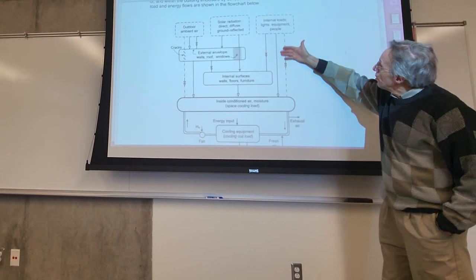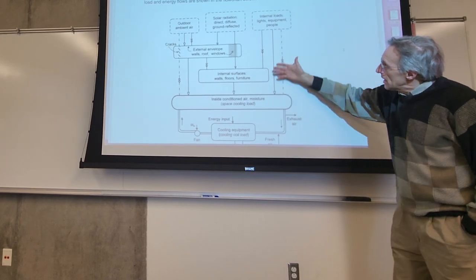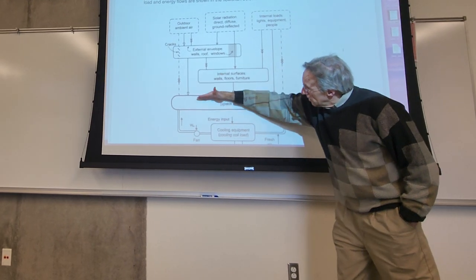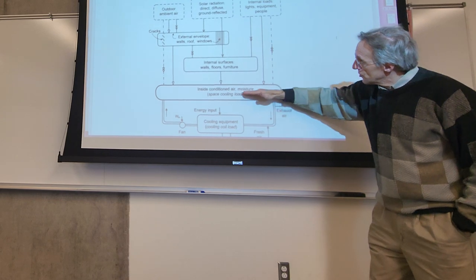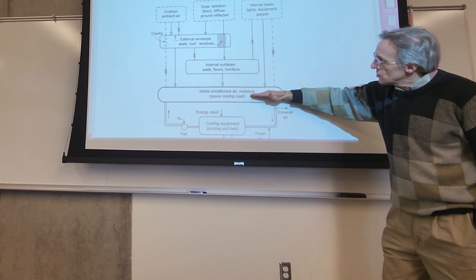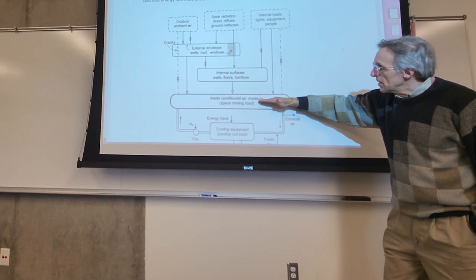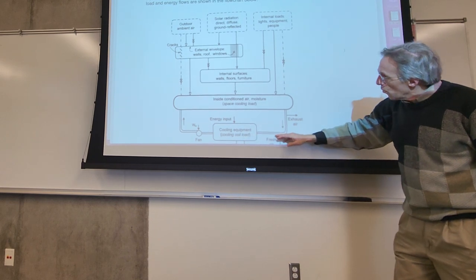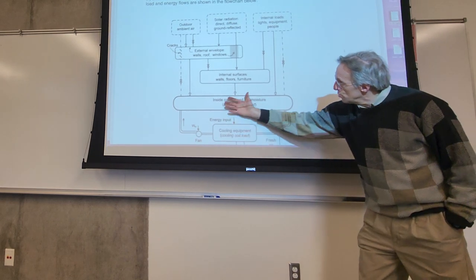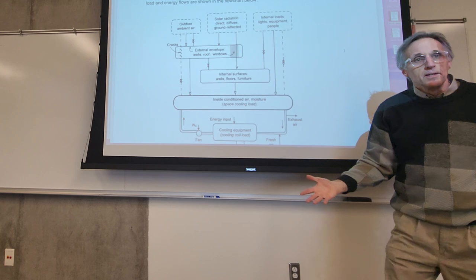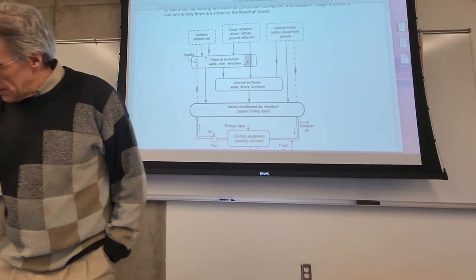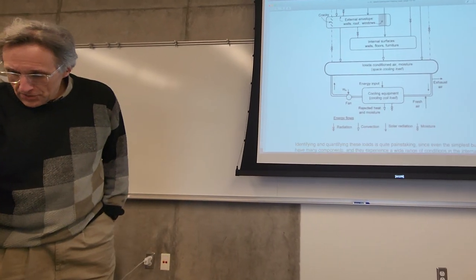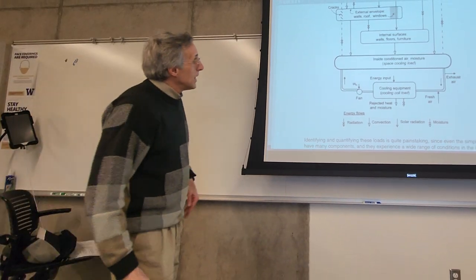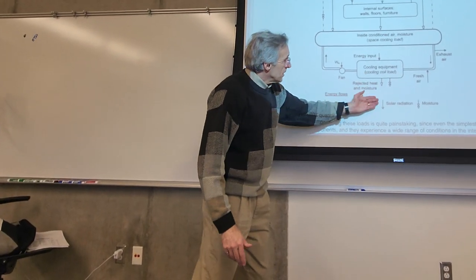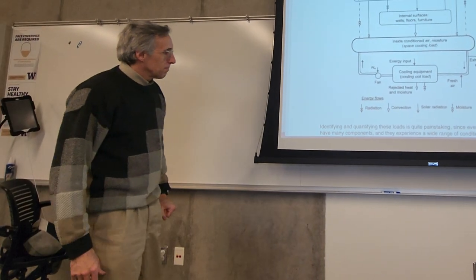You've got the internal loads, all the people and the equipment, and all of that load on our space, moisture and latent and sensible energy. And this is what our cooling equipment has to do. It has to move this energy as it's coming in to keep thermal equilibrium in the space, and then we're rejecting the heat and moisture to the surroundings.